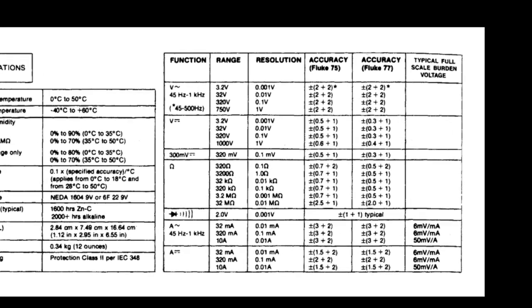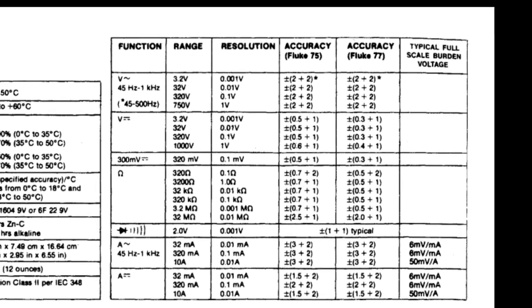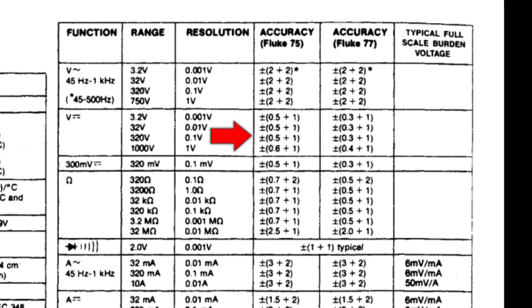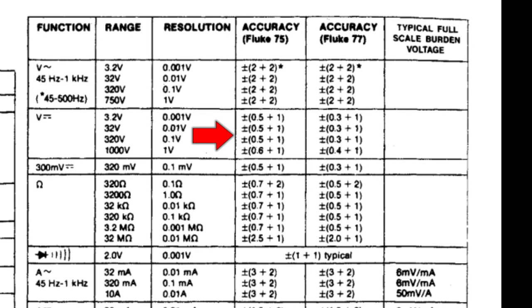Now let's have a look at the specifications of my old Fluke 75, which is no longer in production. We see that the accuracy is affected by the range in two ways. First we have the accuracy specified for each range, and secondly the accuracy is expressed as a percentage of the read value plus a number. This number is the error at the last digit and have to be added to the last digit to compute the actual accuracy for the given range and the read value.